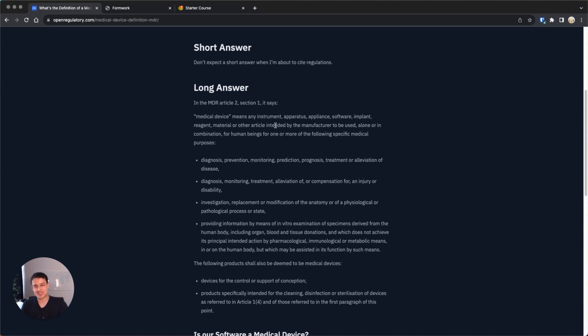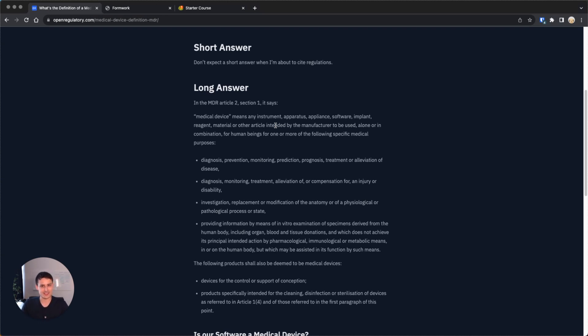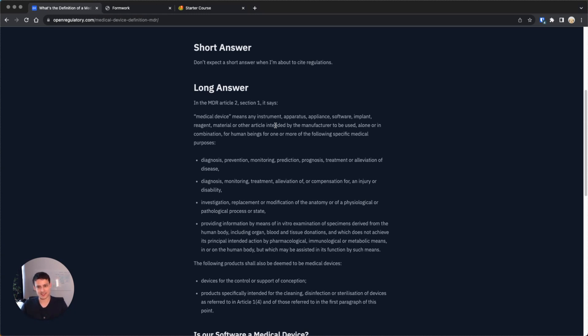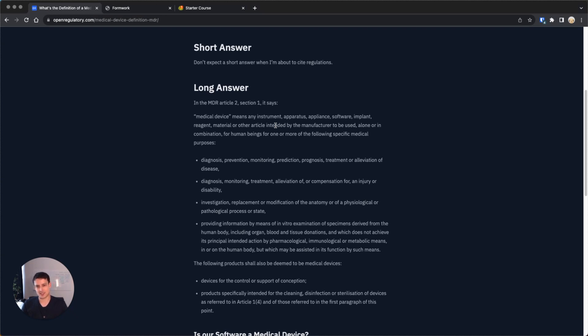Now, the question is, do you need an auditor or not? That's very important, because there are different medical device classes. If you're class 1, and again, this is in the EU, you don't need an auditor. If you're class 2a or higher, so 2a, 2b, or 3, then you need an auditor. There are some edge cases, like some special class 1 devices with a measuring function, which kind of need an auditor.